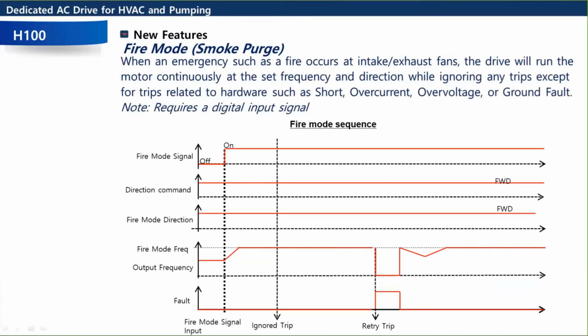Okay, so we're purging the smoke, we're exhausting the smoke out of the building, okay? And we're going to ignore trips, like maybe an external trip or something like that. We're going to ignore trips like that, but we're still going to look at trips like a short circuit, overcurrent, over voltage, ground fault. And the way I think of it is we're still going to look at those trips because those are trips that could cause more fires. So we don't want to add any fuel to the fire if the building's on fire, okay?